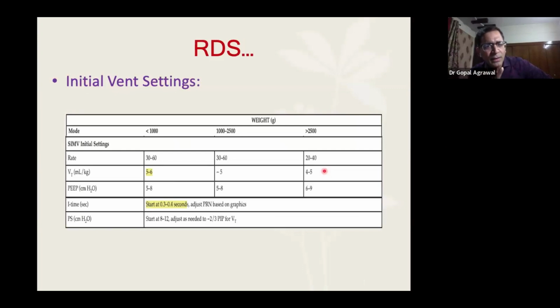The moment compliance is low, the time constant will be low. So by default, the I time will be low. So in any baby whom you feel has RDS, the I time should be set towards 0.3 to 0.4 seconds. A rough rule of thumb is that the initial I time is as per gestation. Suppose a 28 weeker, you have an I time of 0.28. A 32 weeker, you have an I time of 0.32. So the lower the gestation, the lower the I time.